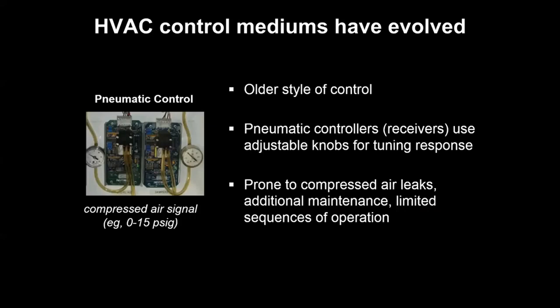But it is subject to a lot of extra maintenance with the compressed air systems, with the air dryers associated at the discharge of that compressed air, and then you have to constantly maintain leaks or have some type of leak detection program in your system, as that will not only use more energy to keep cycling those air compressors, but will start affecting your ability to maintain your sequences of operation.